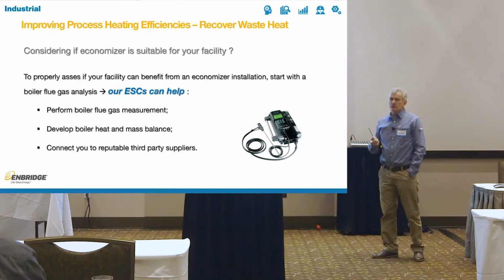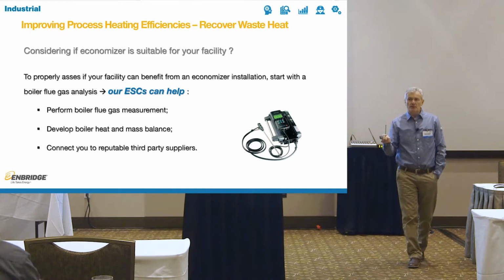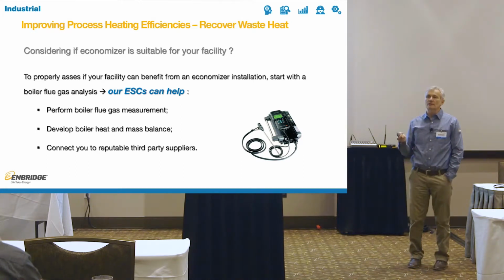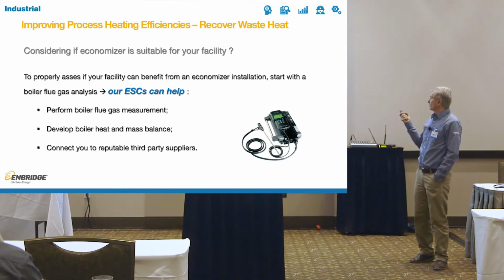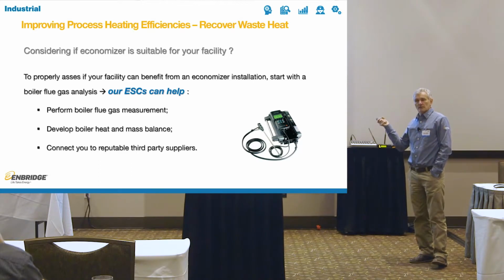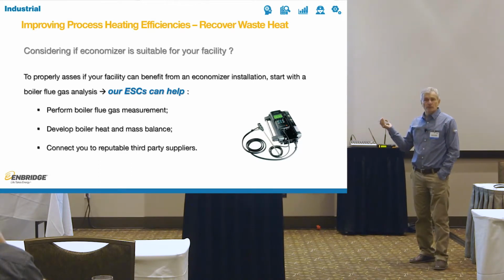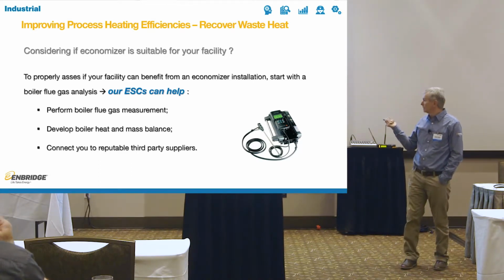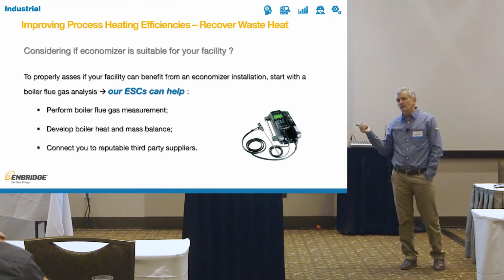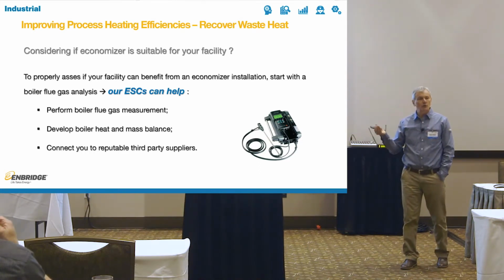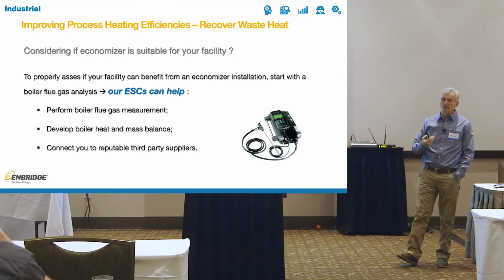So how do you know if condensing economizer, or any economizer for that matter, will help you out? How do you know if you waste energy in your stack? Well, you need to do boiler flue gas measurement. You need to develop boiler heat and mass balance, and then find somebody who will install that for you or give you a quote for it. And all of that can be helped by us.